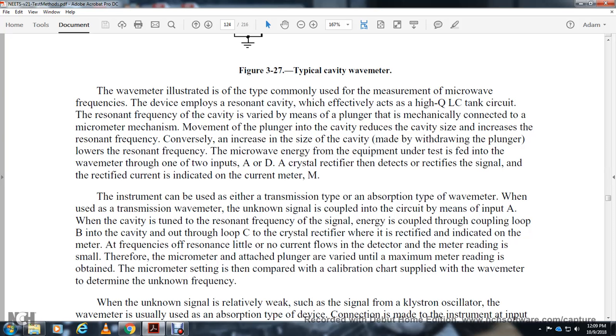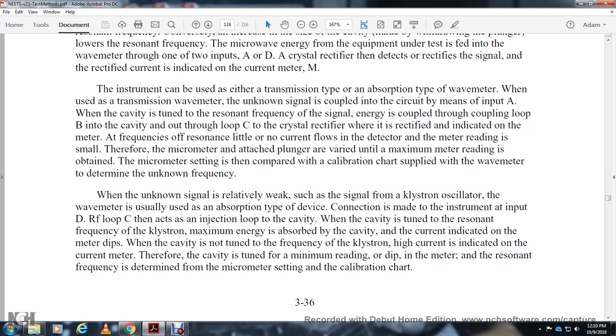In the transmission wave meter, the unknown signal is applied to the input. When the cavity is tuned to the resonant frequency, signal energy is coupled through the coupling loop B into the cavity and out through loop C to the crystal rectifier, and the meter indicates the rectified current. At frequencies off resonance, little or no current flows in the detector, and the meter reading is small. Therefore the micrometer is varied with the plunger until the maximum meter reading is obtained. The micrometer setting and calibration chart supplied with the wave meter determine the unknown frequency.